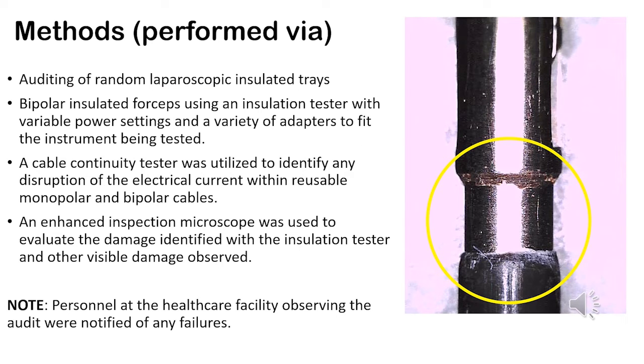For the methods, it was an audit of random laparoscopic insulated trays and bipolar insulated forceps, using an insulation tester with variable power settings and a variety of adapters to fit the instrument being tested. A cable continuity tester was utilized to identify any disruption of the electrical current within the reusable monopolar and bipolar cables. An enhanced inspection microscope was used to evaluate the damage identified with the insulation tester and other visible damage observed. And just as a side note, personnel at the facility during the study were notified of the failures.